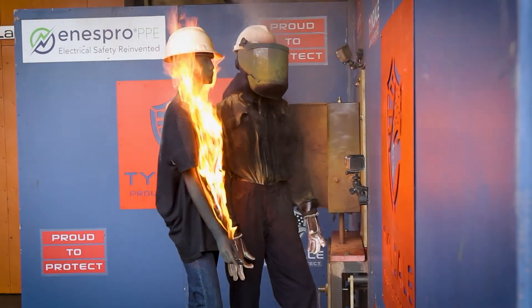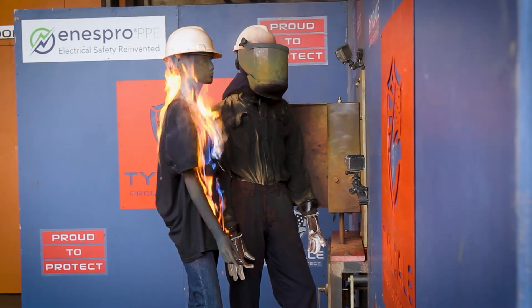We'll roll our slow motion first. As you can see, the arc does impact the female mannequin, but only barely before retreating again. In real time, she's instantly on fire. So that arc was more than enough to ignite that flammable clothing, even though she was at a significantly greater distance, particularly than the left shoulder of the mannequin.